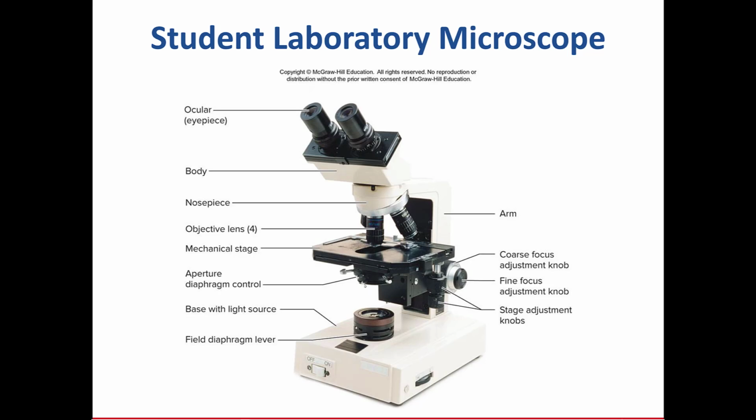This adjusts. This is sort of, if you use cameras, this is your f-stop. You adjust the aperture, and that adjusts how much light actually gets in. The light source down here, and you can dampen this. There's various, depends on the scope. You can adjust the brightness by how much voltage goes to the light source here. Sometimes they have an adjustment that opens and closes an iris, so how much light gets through and that sort of thing, and it's there. So you usually have, between these two, you can adjust the amount of light that actually gets into the camera.